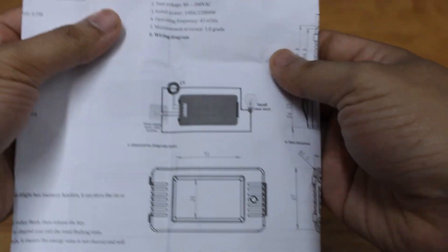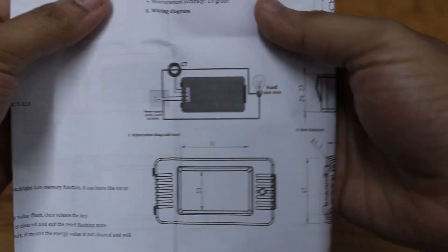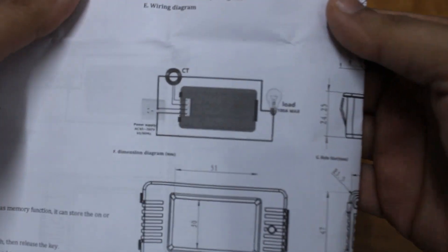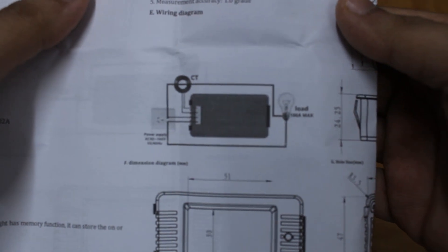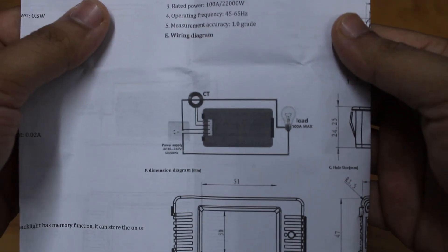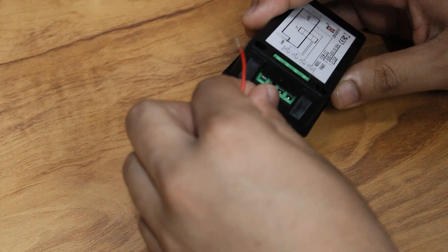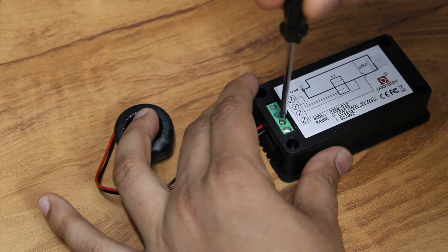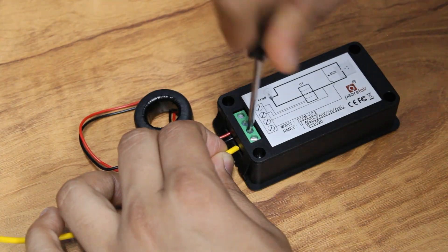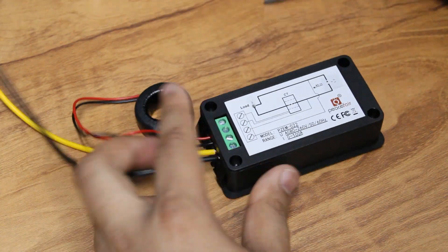To use the device, power it using AC mains. Simply pass a wire through the transformer and connect to the load, and you will get the readings. Make sure you are passing only one wire and not both. This is not possible with a shielded multiple core cable.